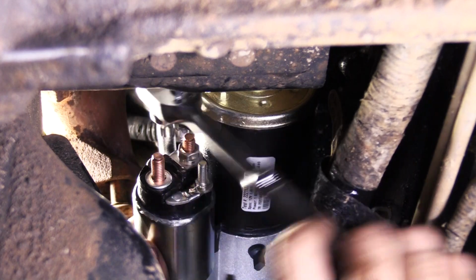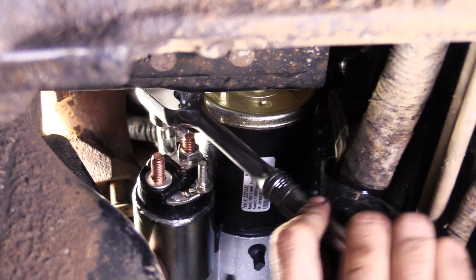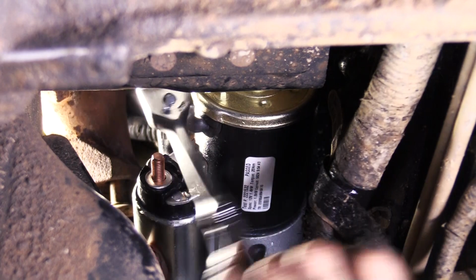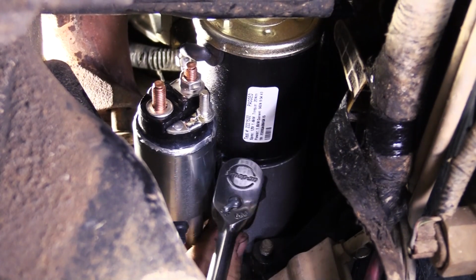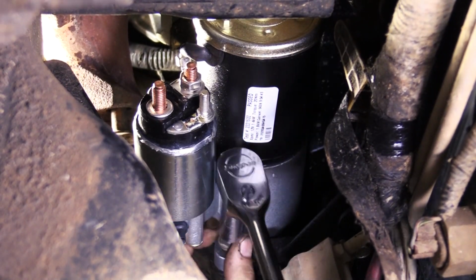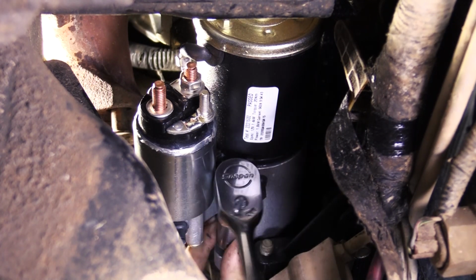Now those bolts have to be torqued to 18 foot-pounds. That's key, 18 foot-pounds for all 3, including the bottom stud. Remember that bottom stud down there? Get that torqued, and then you have to reattach the ground there.